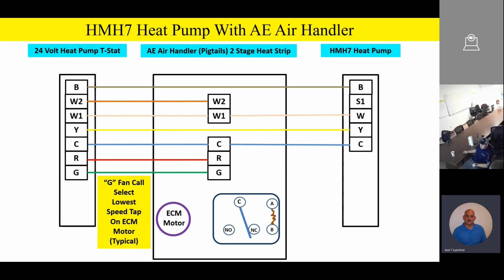And then the G terminal will go from the thermostat to the indoor unit. And again, typically, on a G call, you're going to select the lowest speed tap on the ECM motor. That would be very typical. So you're going to be setting up some speed taps on the motor. That's important that you understand that. When you're setting these things up, you're going to be setting up the speed taps on the motor, and G call is typically going to be the lowest speed tap on the ECM motor.